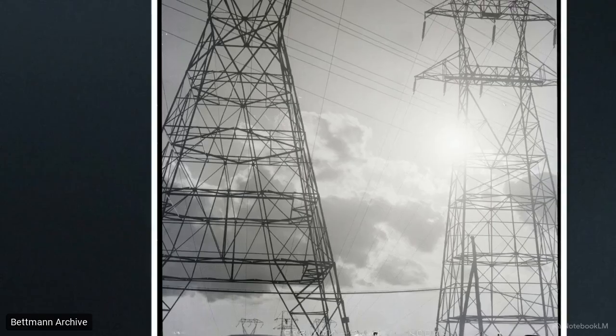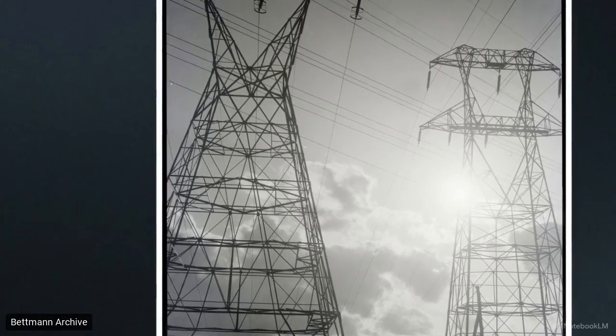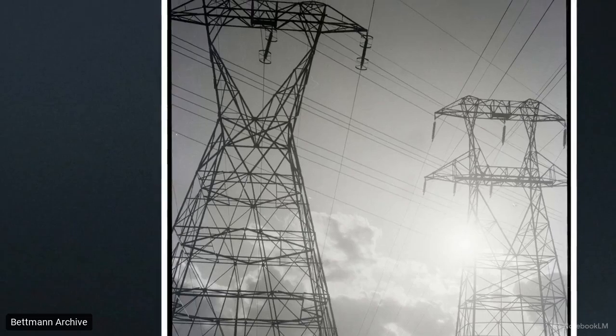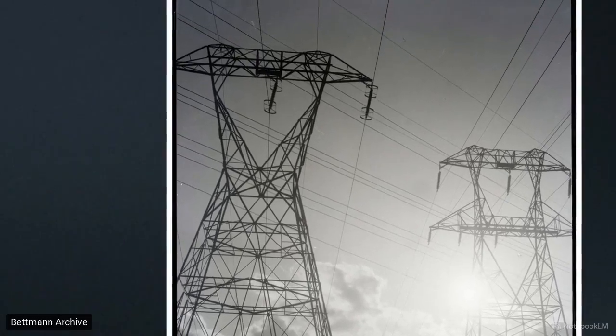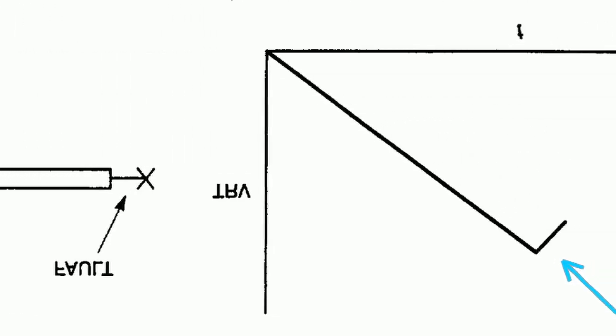But shift that fault out onto a transmission line, a scenario known as a short-line fault, and the physics change completely. Here we see a much more violent characteristic. The fault creates traveling waves that bounce back and forth between the open breaker and the fault location, generating a brutal sawtooth waveform with an incredibly high rate of rise. Looking at the breakdown of this sawtooth wave, the source side voltage rises relatively slowly. The real danger comes from the line side, which creates that extremely fast, aggressive triangular spike.